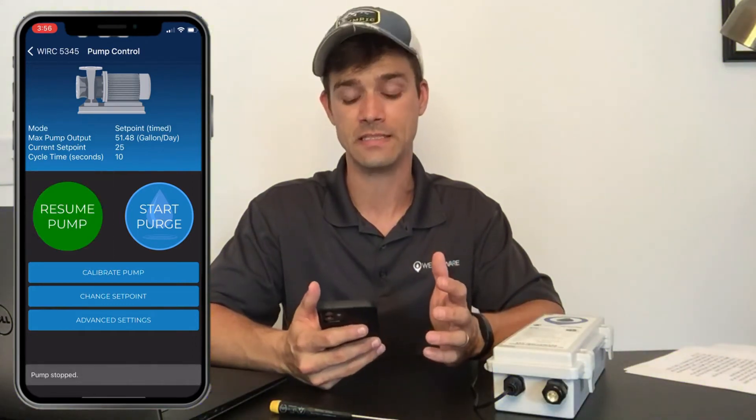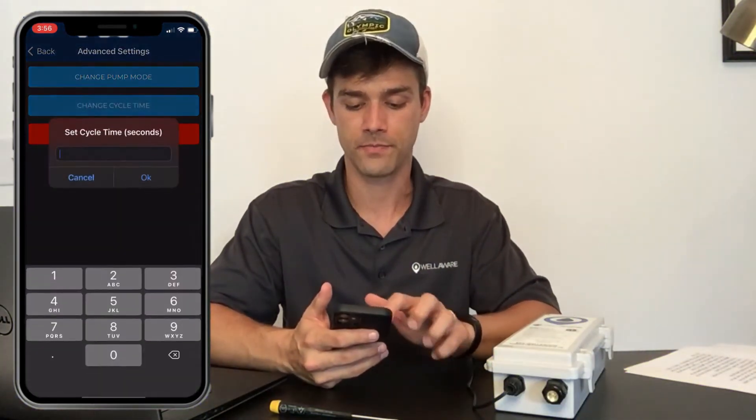The WellAware Field app gives quick pump controls. I can stop the pump and the LED turns off, then resume it back to its normal set point. I can also purge the lines — sometimes a line fills with air and you need to run the pump full bore. Starting a purge keeps the LED on continuously. As soon as I stop the purge, it returns to normal operation: five seconds on, five seconds off. I can also change the cycle time — setting it to five seconds means it'll run two and a half seconds on and two and a half seconds off.